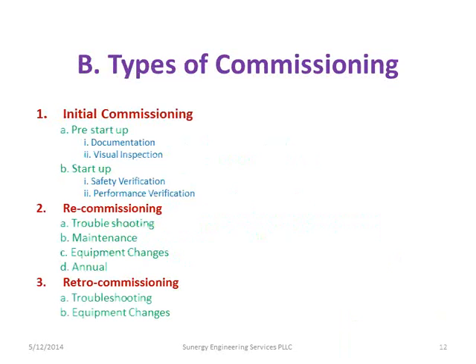There are several types of commissioning. There's initial commissioning, a startup commissioning, where you go in and do the initial startup of a project before handing it over to the owners. That's the full enchilada - the whole commissioning, going through all the paperwork and design work, making sure everything was done as specified to the customer. Of course, in a home system, that's not nearly as detailed as it would be on a large megawatt system.